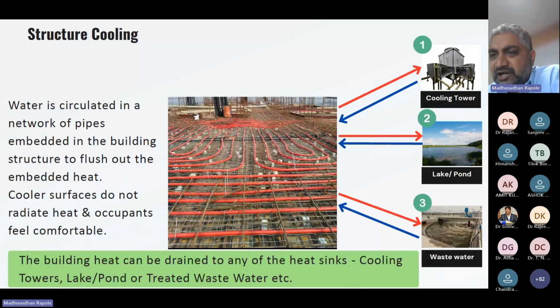That's it. There could be multiple heat sinks you can think of. The simplest one could be using a cooling tower. We use a multi-stage cooling tower. It could be a water body. It could even be a treated wastewater tank. I'm not saying we will use this water and circulate it in this. I'm saying we can indirectly dump this heat. We can use this as a heat sink by immersing a heat exchanger or a network. So that's all structure cooling does. It does not allow heat to accumulate, it flushes the heat, so that for people occupying the space, we are bringing down the mean radiant temperature.